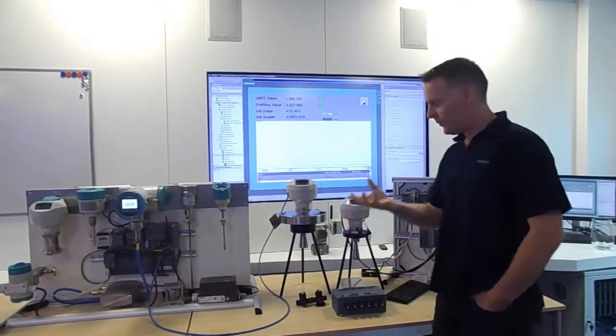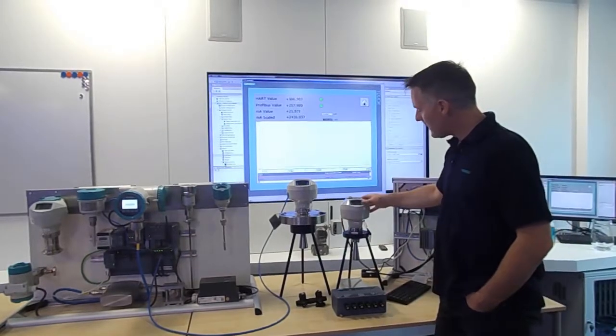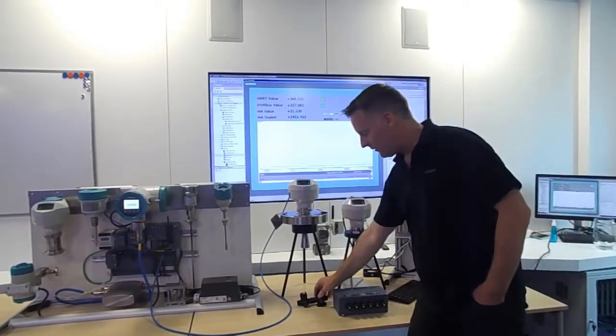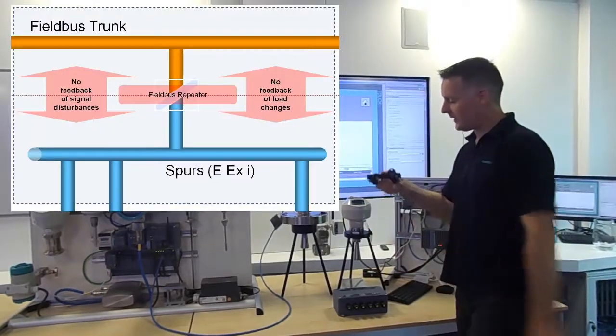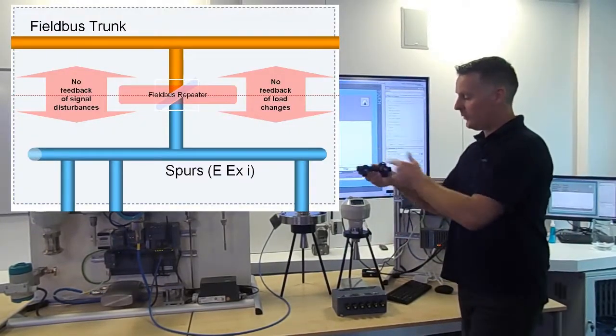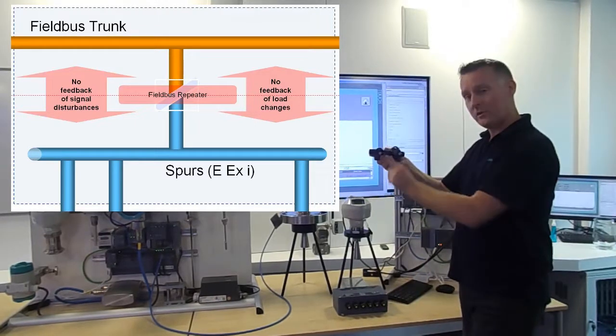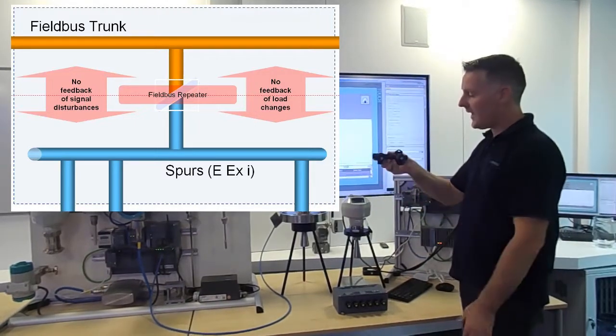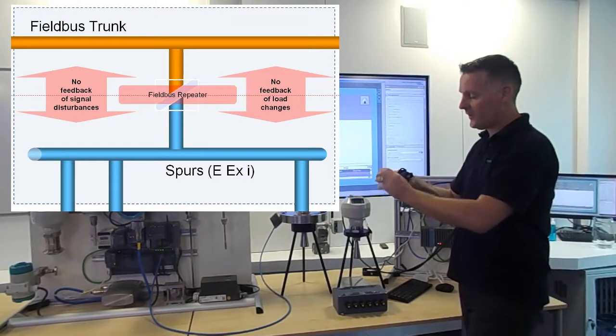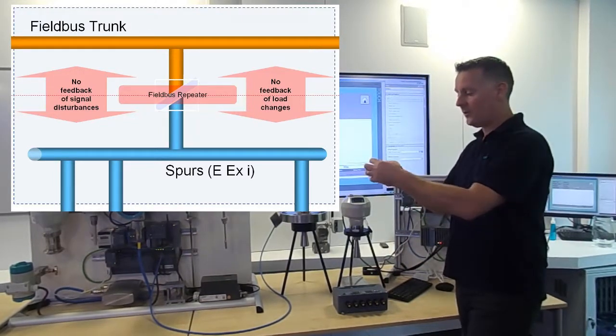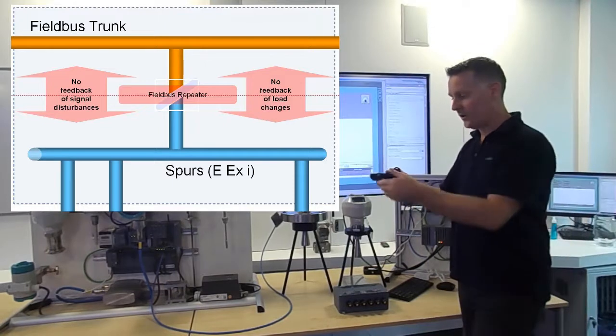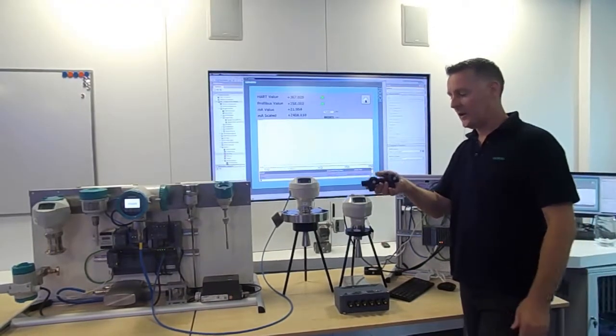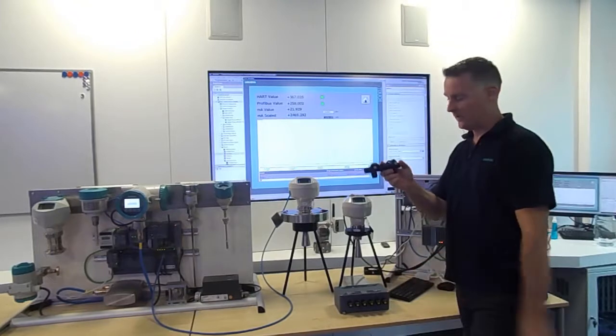And there's still things to worry about with your Profibus signals. I'll use this as an example of a low cost split connect. So this is what we call a T and your Profibus spurs come off. If you got water into here it would work but as these spades started to corrode you could end up losing the whole of your network. It's a low cost solution but can mean high cost maintenance.